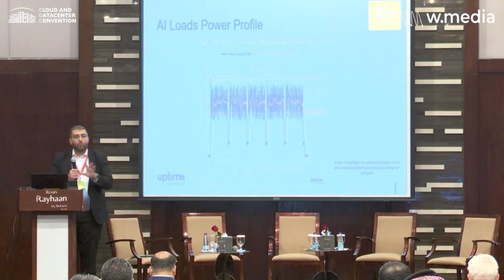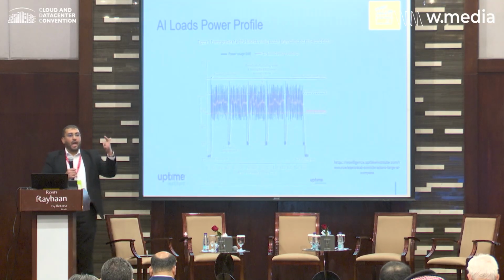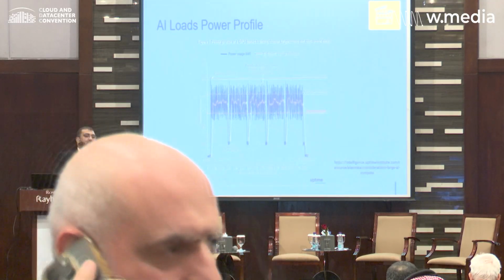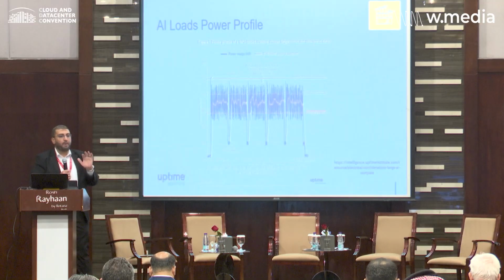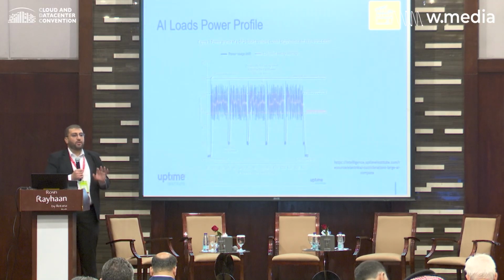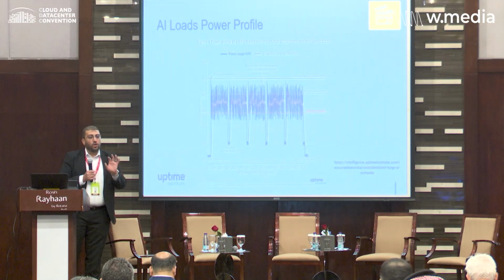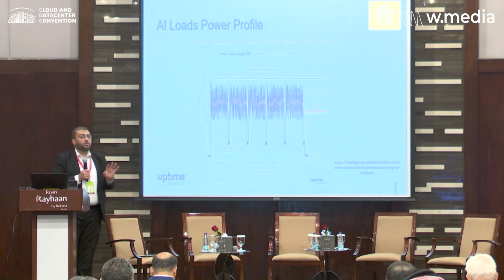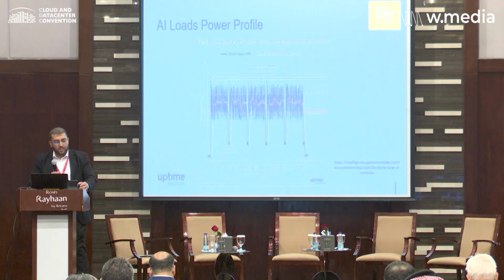So you need to make sure at the design stage to select the right type of equipment that's capable of handling this AI workload model, and to make sure that during testing and commissioning you have the full load by using the special load bank to simulate this AI load transient, to make sure your facility is ready to receive the AI workload.